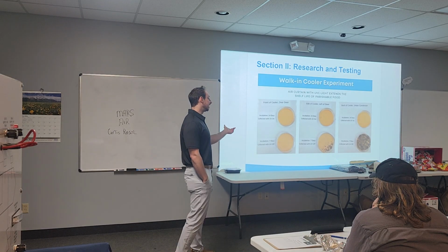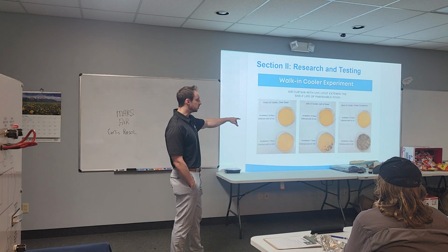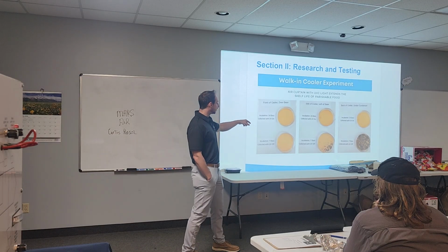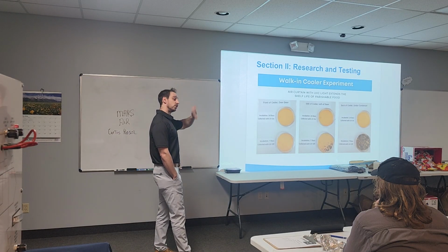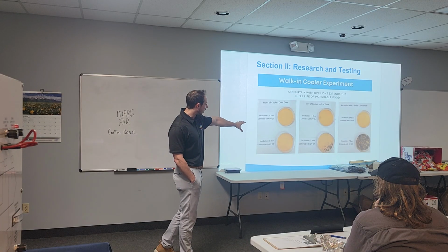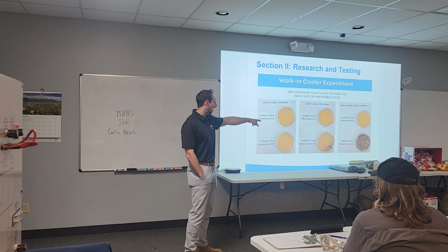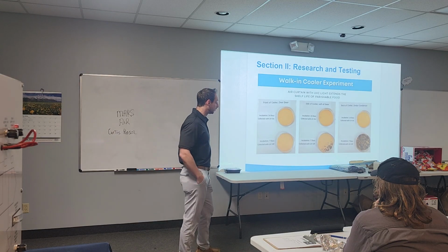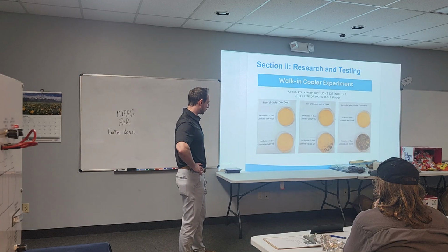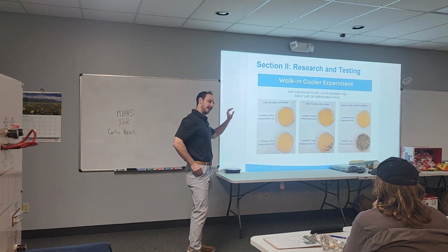So the idea here was we put two sets of Petri dishes in a cold storage room. The first set, on the bottom, we left in for a week with our air curtain off and UV feature off, and that was the mold growth that accumulated, especially under the condenser in the back. A pretty crazy amount of mold growth, which was interesting because that's where all the food is being stored, at least for that restaurant. So yeah, it was kind of interesting.